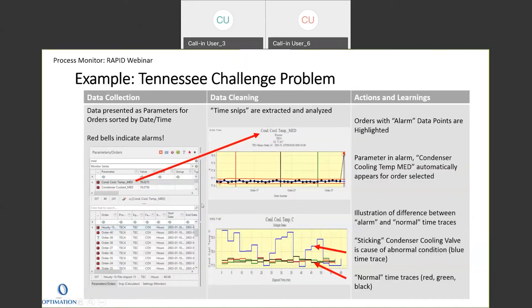Here's an example where we have different orders — lots of different batches of chemical were made, and one that was in alarm was the condenser cooling temperature. There are control chart limits here for most of the batches, and there's one that was a lot higher than the others. The median temperature was less than a degree different, but it is higher. We've highlighted the four batches shown here — red, black, green, and blue — and here are the time traces for each of those batches.